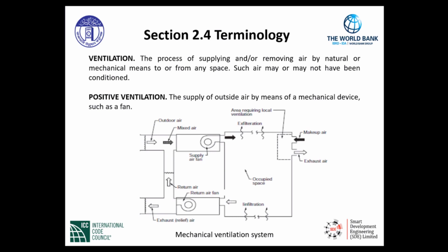In the upper left-hand portion of the diagram, we can see the entry of the outside air. It is mixed with the return air at a certain volume and supplied into the supply air fan and then distributed into the occupied space. The air is returned through the bottom of the graphic into the return air fan. We have an exhaust, relief air, and return air moving back up and then mixing again with the outdoor air to provide good, clean, filtered air into the occupied space. And this is a good example of a mechanical ventilation system and air conditioning system.